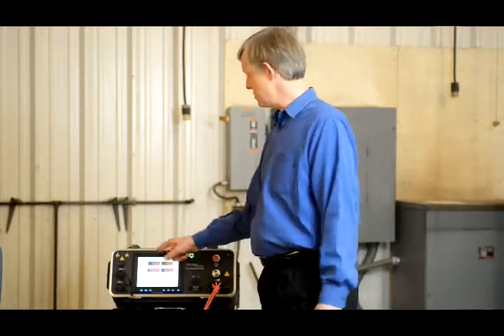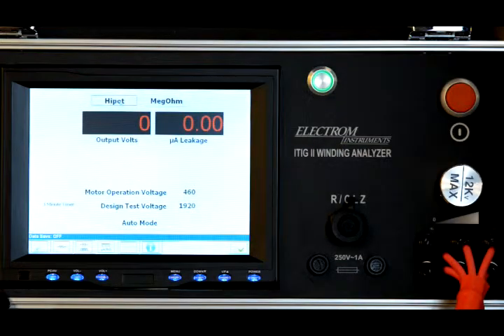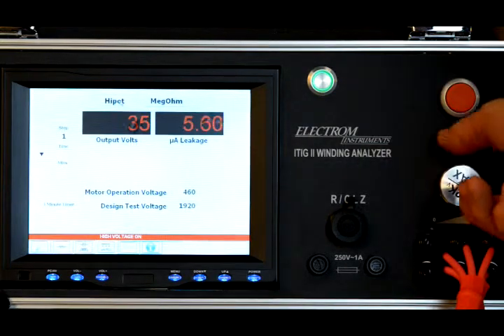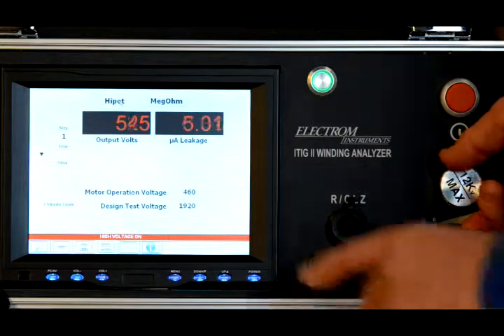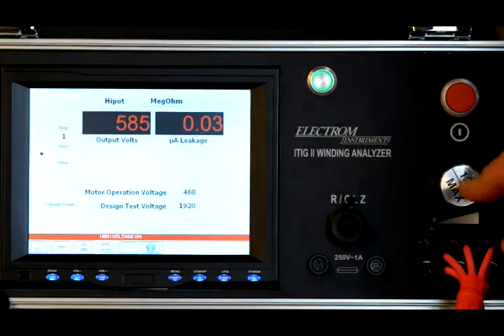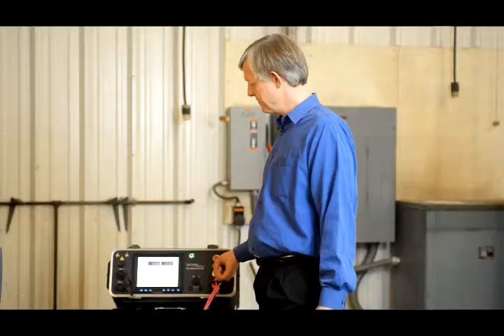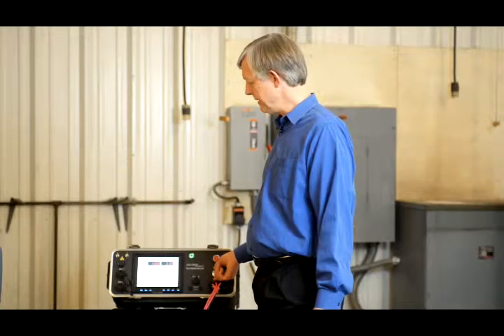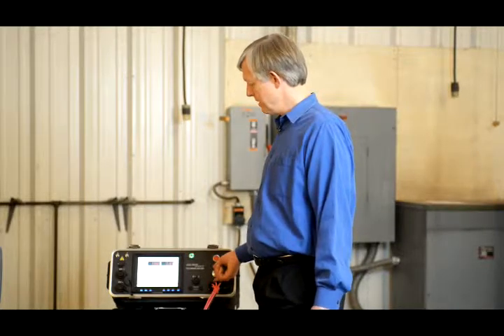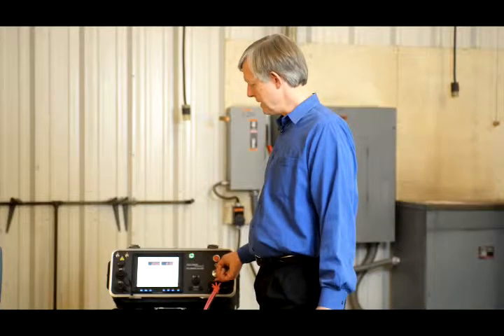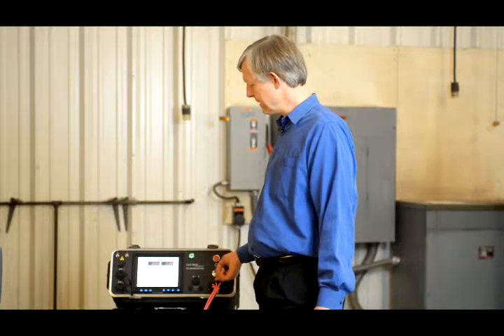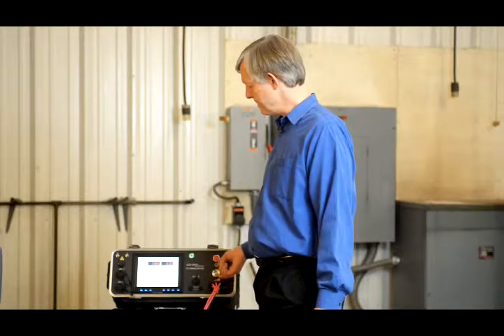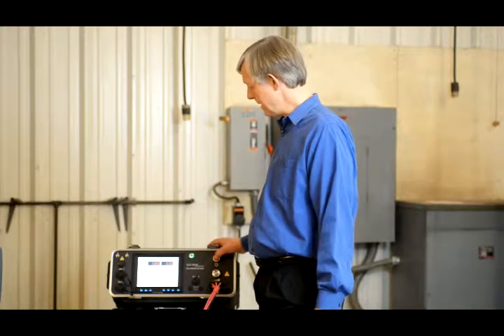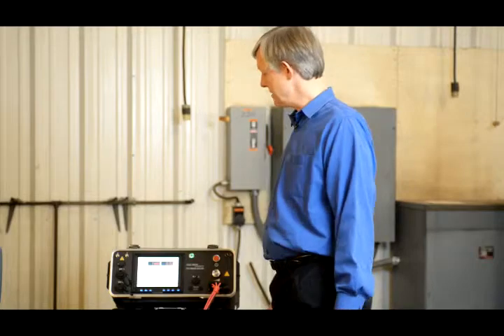We move on to the next test, which is the hipot test. It's essentially the same as the megohm test. We click the start button and dial up the voltage. Now we're going to dial it up to the design test voltage, which is calculated by that formula on the setup screen. Again, we should hold hipot for about a minute. We're not going to do that here, but again, we see that this is a pretty good motor. There is essentially no leakage current, and we turn it off and the test is done.